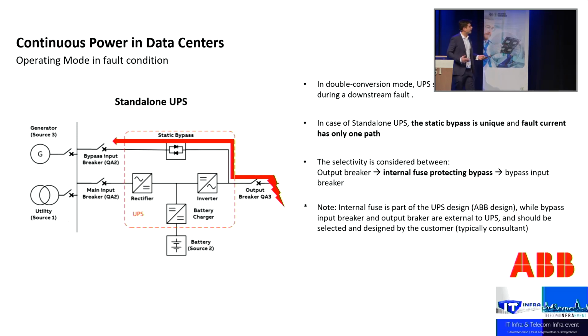So let's analyze if I have a failure downstream of the UPS. In the case of a standalone UPS, which is, by the way, an easier thing to handle, I would have the fault downstream of the UPS. My fault current would run through the circuit breaker, which is downstream and external to the UPS, so it's not inside of the UPS design, through the static bypass and through the fuse. This is very important, through the internal fuse, which is protecting the bypass, and then through the bypass breaker. So I need to analyze selectivity basically between those 3 devices. And then the rest of the selectivity I can do in more traditional ways or using the software tools that are used for analyzing the selectivity between the breakers.